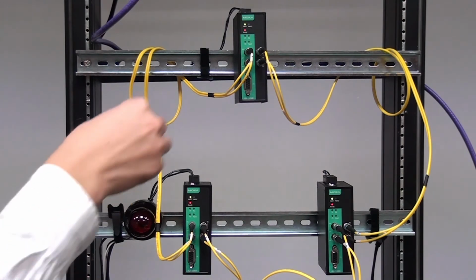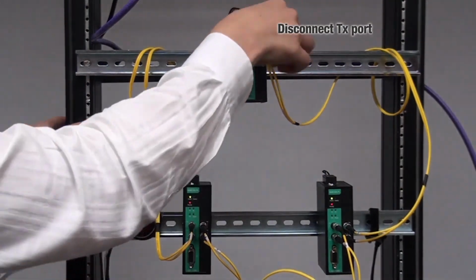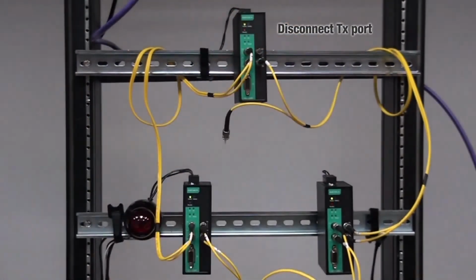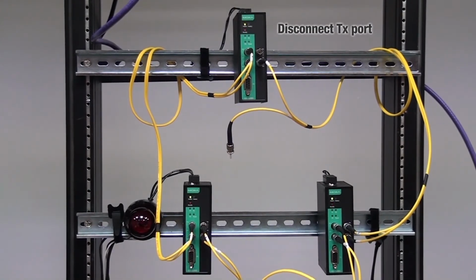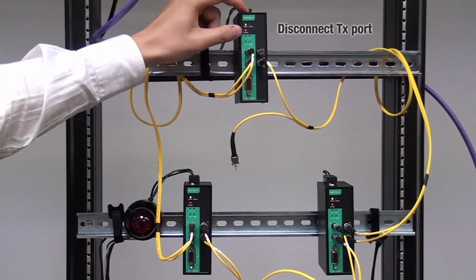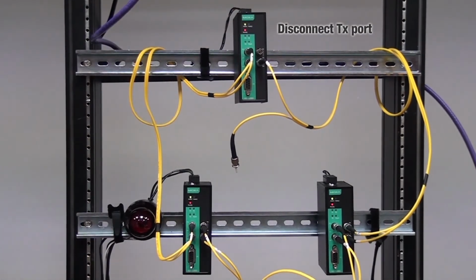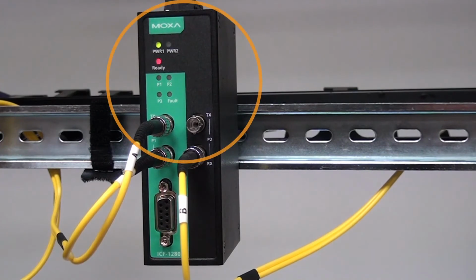For our first test, we'll disconnect this cable from the TX port on the top converter. Then we will activate fiber diagnosis by flipping DIP switch 8 to on. The ready LED will flash red while fiber diagnosis is running. It will turn green when the test is complete.